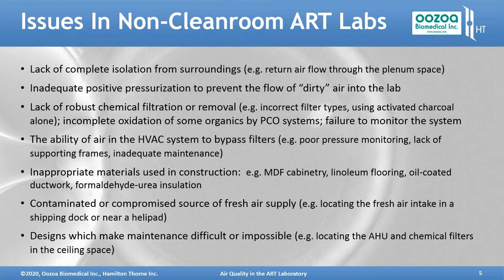PCO systems will only result in partial oxidation of VOCs at each pass, so you will have incomplete oxidation of some organics, and that might create some aldehydes, for example. And you typically are not monitoring your HVAC system in a non-clean room environment. The air in the HVAC system in non-clean room spaces is also often able to bypass the filters due to poor pressure monitoring, lack of supporting frames of filters, inadequate maintenance, etc. And inappropriate materials are often used in construction.